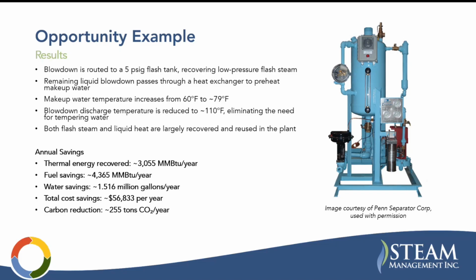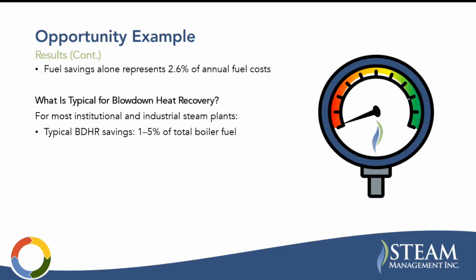Annual savings here is 3,000 million BTUs per year. Your fuel savings is basically that divided by your boiler combustion efficiency. You're getting 4,365 million BTUs per year. Significant amount of water, but the punchline here is this is almost $57,000 per year in savings and 255 tons of carbon per year. That's a significant amount of savings. The fuel savings alone represent 2.6% of the annual fuel costs of the system.